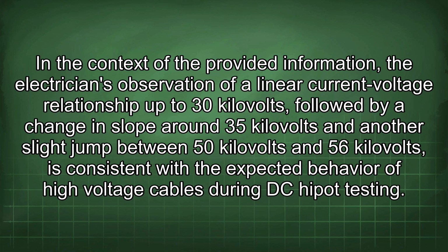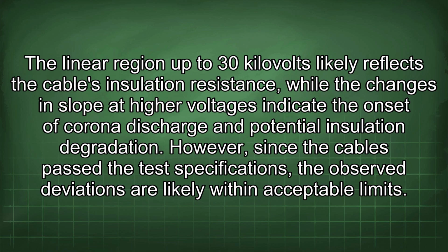In the context of the provided information, the electrician's observation of a linear current voltage relationship up to 30 kV, followed by a change in slope around 35 kV and another slight jump between 50 kV and 56 kV, is consistent with the expected behavior of high-voltage cables during DC hipot testing. The linear region up to 30 kV likely reflects the cable's insulation resistance, while the changes in slope at high voltages indicate the onset of corona discharge and potential insulation degradation. However, since the cables pass the test specifications, the observed deviations are likely within acceptable limits.